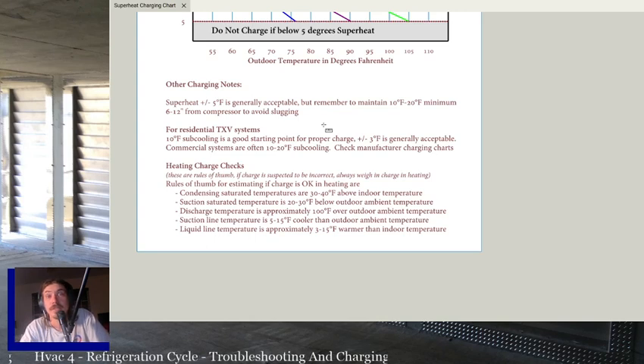If your saturated temperature on your condensing side, your indoor unit in heat mode, is not 30 to 40 degrees above indoor temperature, we're not going to be able to give off much heat, right? Our condensing temperature has to be higher than the temperature we're trying to give off heat to. So if it's 70 degrees inside, we should have a saturated temperature in the condenser of 100 to 110. Otherwise, we're not giving off any heat. We can't subcool it before we send it outside, right?